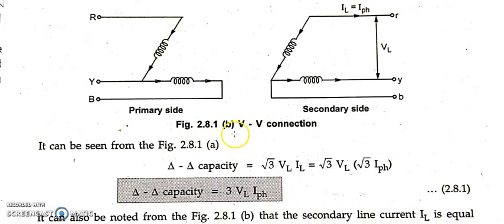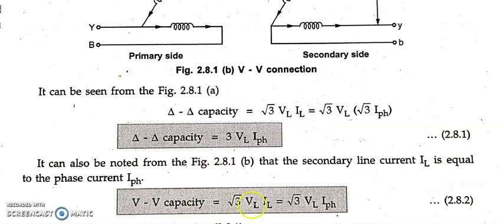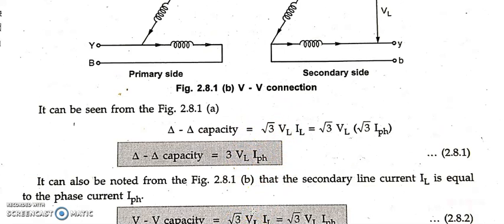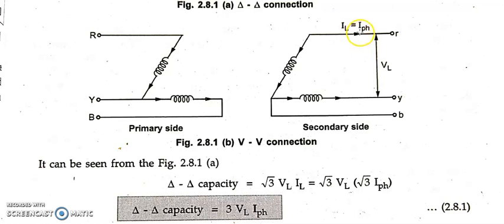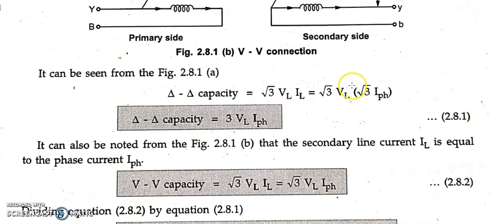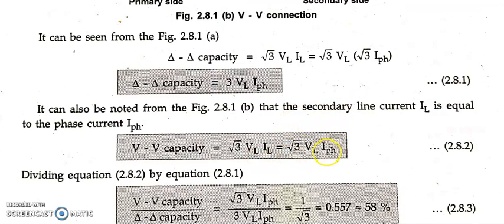Now coming to the second figure, for VV capacity. You can see for VV capacity, again the formula remains the same, root 3 VL into IL. This is the traditional formula which always remains the same for any 3-phase transformer. So root 3 VL into IL. But now see what we have got as the formula for IL as well as I phase. Anyhow the current is not getting divided, so what happens? IL is equal to I phase. Before it was IL equal to root 3 times I phase.